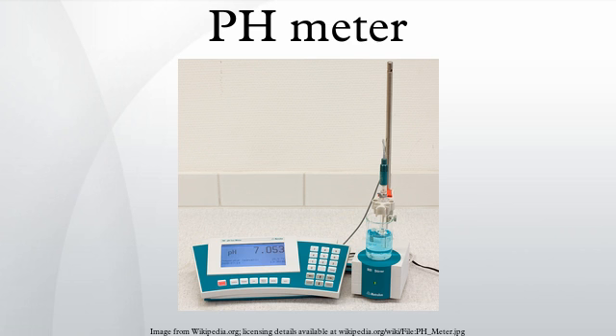Calibration and use. For very precise work the pH meter should be calibrated before each measurement. For normal use calibration should be performed at the beginning of each day. The reason for this is that the glass electrode does not give a reproducible EMF over longer periods of time. Calibration should be performed with at least 2 standard buffer solutions that span the range of pH values to be measured. For general purposes buffers at pH 4.01 and pH 10.00 are acceptable.